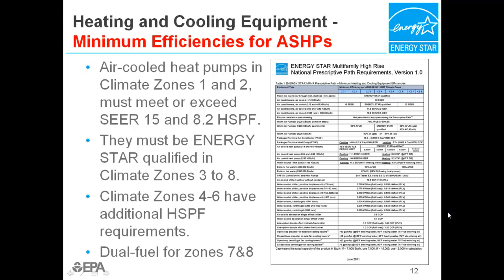Split system air-cooled heat pumps between 13,000 BTUs per hour and 65,000 BTUs per hour must be minimally Energy Star qualified in all climate zones. In climate zones 1 and 2, they must exceed Energy Star criteria with at least a SEER 15 and 8.2 heating season performance factor. Climate zones 4 through 6 have additional heating season performance factor requirements, and in climate zones 7 and 8, the Energy Star qualified heat pumps must have dual fuel backup rather than electric resistance backup.